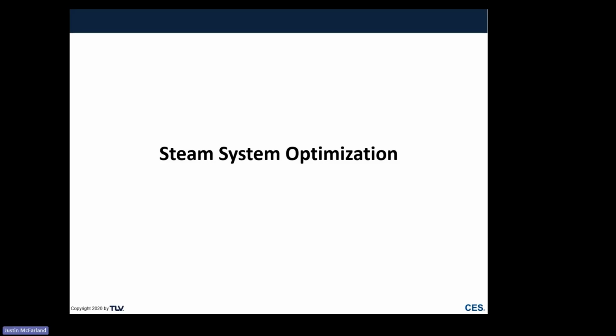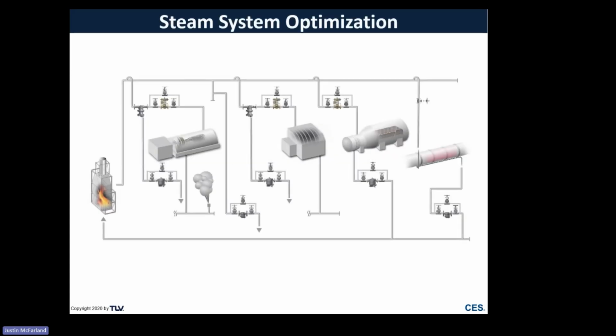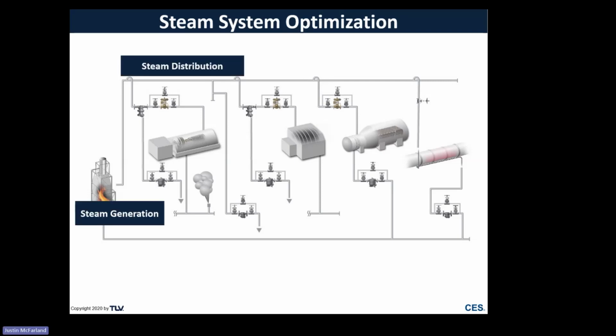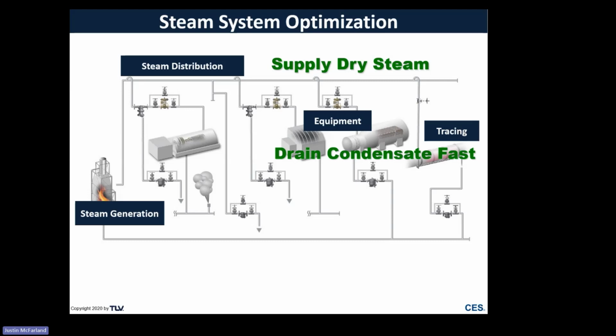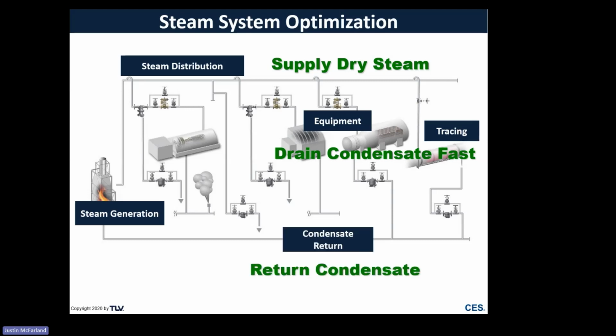So, steam system optimization. This is really what we're talking about today. From a 3,000 foot elevation view, when we look at a steam plant, plants of all shapes and sizes, they vary, but for the most part, we have steam generation in a boiler. We're going to distribute that steam throughout the plant. The idea here is we want to supply dry steam. That's going to go to various pieces of equipment, tracing, turbines. We want to drain condensate quickly and then return that condensate. Condensate in a steam system, it's not good. They don't mix. Things go boom. So we want to get rid of the condensate and then return that back to the boiler to be an efficient system.